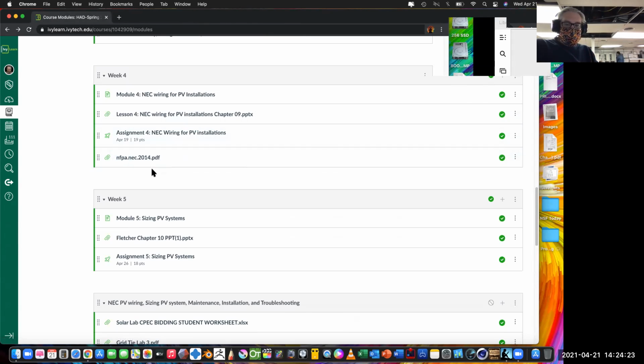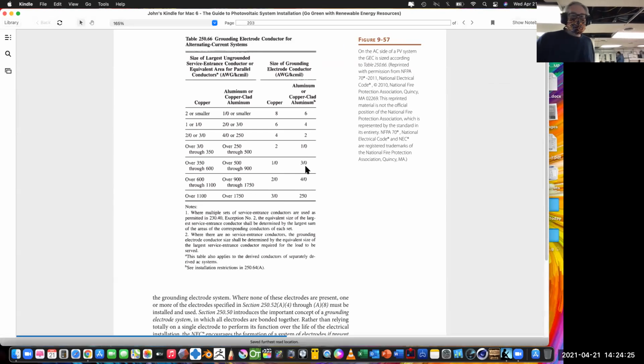All right, so let's go back to our book here. What we're learning is how to size our wire. So we chose number 6, is what I'm pointing out, and I told you why we chose number 6. Now, because we know the size of our power cables for our system, number 6, we know it can handle 60 amps, which we have 60 amp breakers all over the place limiting our ability. That thing is pushing 5,000 watts.